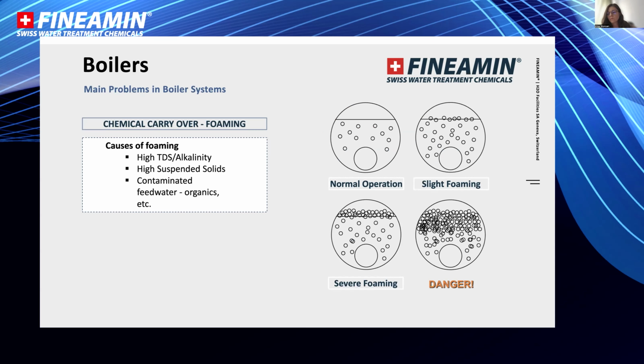Then the third point is about the steam quality. So what is this quality for the steam that can tell us? In case we have a problem called carryover, then the steam quality will be affected. That means the boiler water will be sucked into the steam lines in the form of fine droplets. So we have two reasons. One is mechanical carryover, known as priming. And the second one is chemical carryover, that is known as foaming.